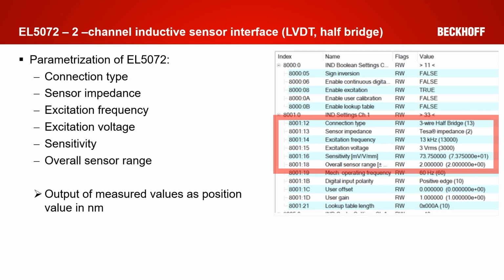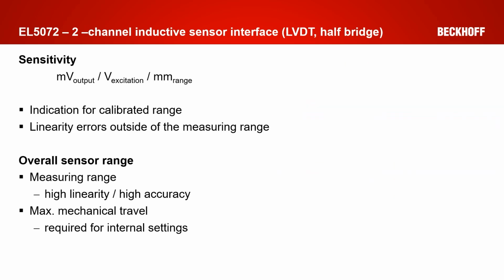Now we can look at the last parameters, the sensitivity and the overall sensor range. The sensitivity indicates the ratio of the output voltage to the supply voltage and to the traveled measurement distance. This is the main conversion factor for the terminal to calculate the position value out of the measurement signal voltages. In the main cases, the sensitivity is valid for the calibrated range of the probe. So outside this measuring range, linearity errors can occur.